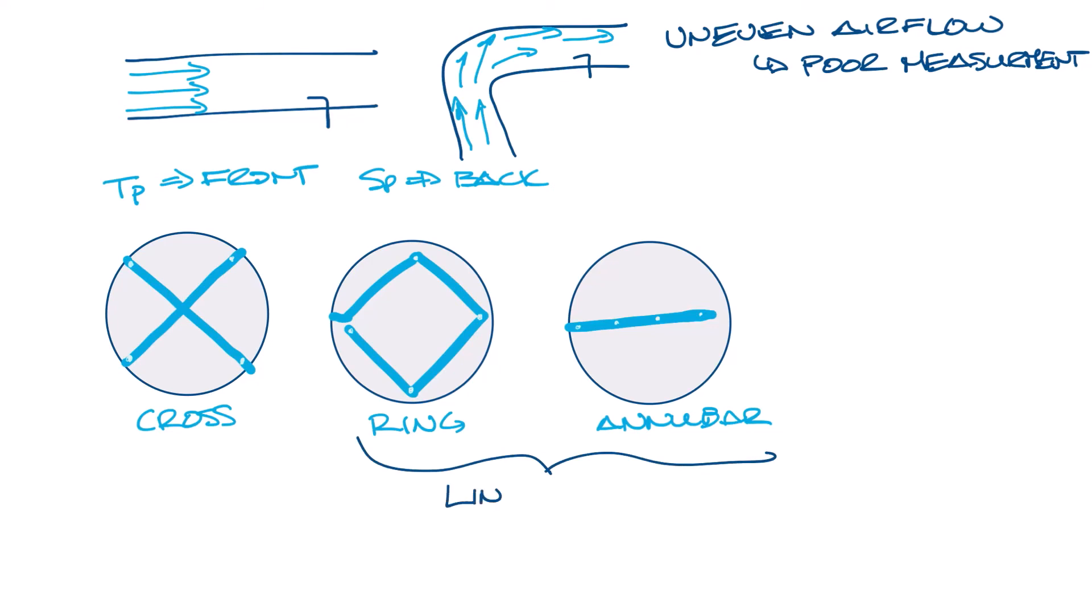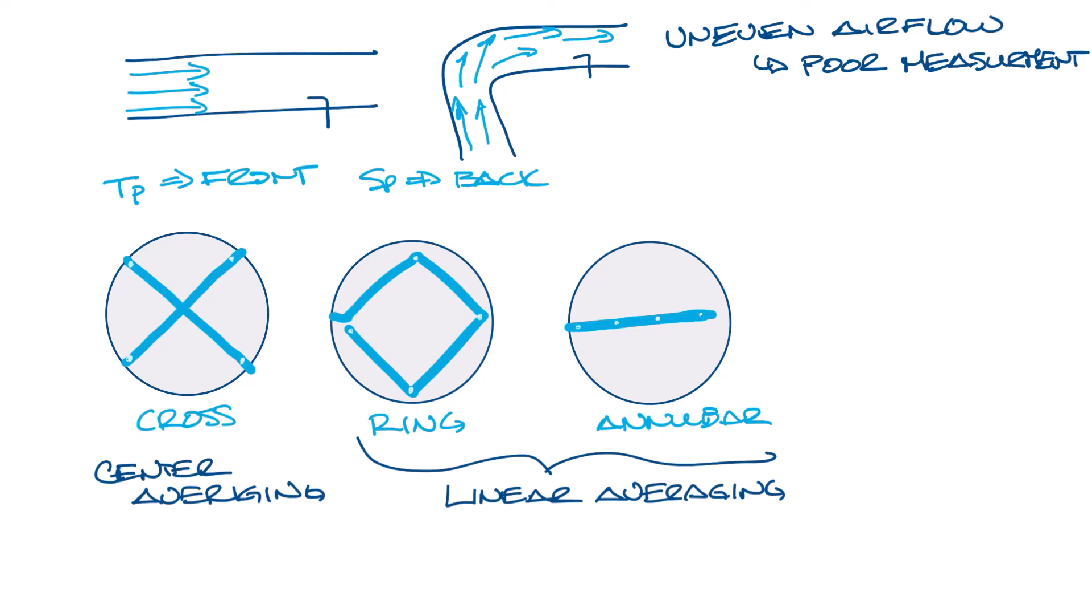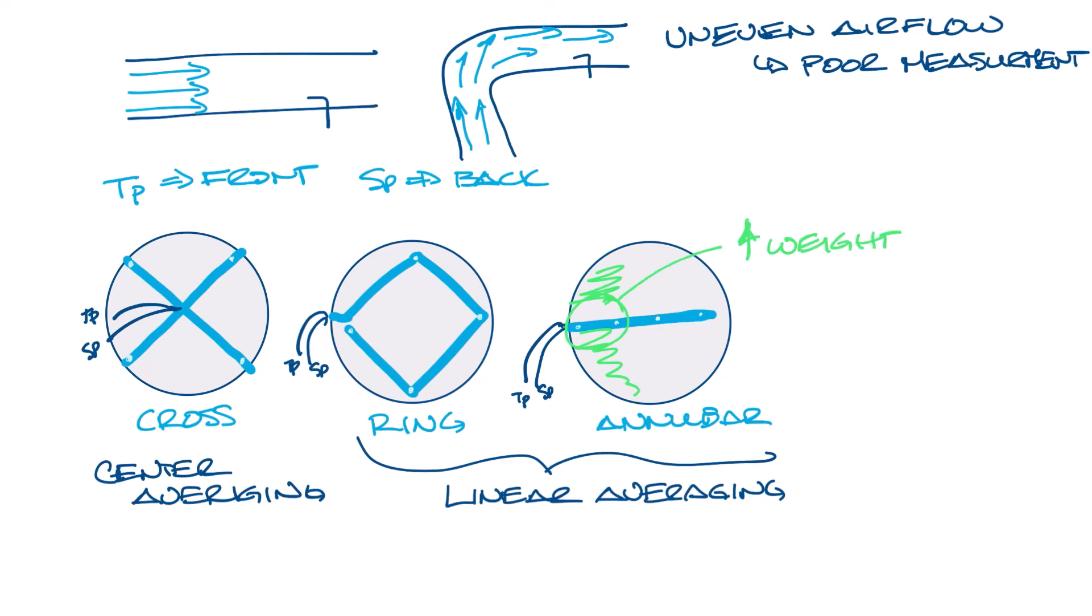The flow ring and anubar sensors are linear averaging flow sensors. And the flow cross is a center averaging flow sensor. So linear averaging means that the measurement is taken at one end of the sensor. So if you imagine the ports come out here and are measuring total pressure and static pressure in these two and in the flow cross it's coming out the center. So when you look at how airflow goes into the ductwork if you end up with a situation with bad inlet conditions and all the airflow piles up on this side you can see that these two ports would have a higher reading and would probably have higher weight in the average. Same thing with the flow ring because you're taking the readings on one end of the sensor. Now in the flow cross if it piles up on one side you're taking the reading in the center so one side may be high and one side may be low but is averaging at the center and you tend to get a more accurate reading especially in bad inlet conditions.